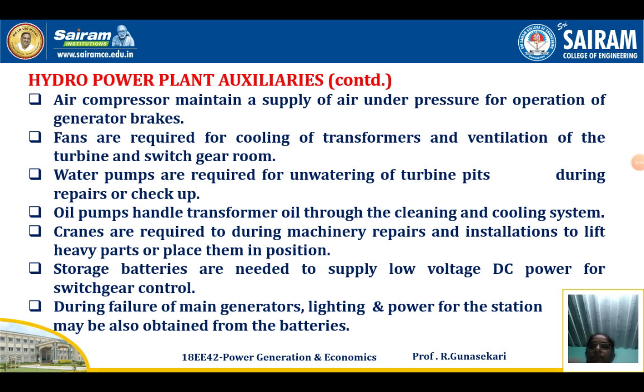Air compressors maintain a supply of air under pressure for operation of generator brakes. Fans are required for cooling of the generators and ventilation of the turbine and switchgear room. Water pumps are required for dewatering of turbines during repair or checkup. Oil pumps handle transformer oil through the cleaning and cooling system.